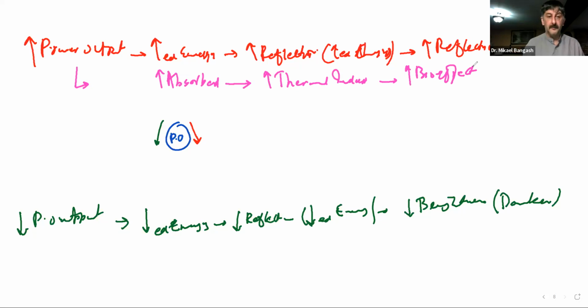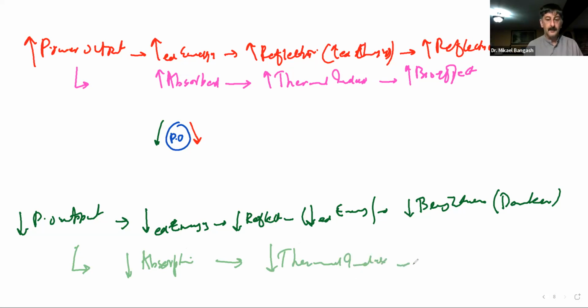The exact opposite applies if we bombard tissue with a lesser amount of energy. That means that as the sound travels through the same tissue as we had up here, there would be a lesser absorption. Lesser absorption means, to some extent, a lesser thermal index. And the lesser that thermal index is, the lesser the likelihood of bioeffects. So that's two sides of the same coin.